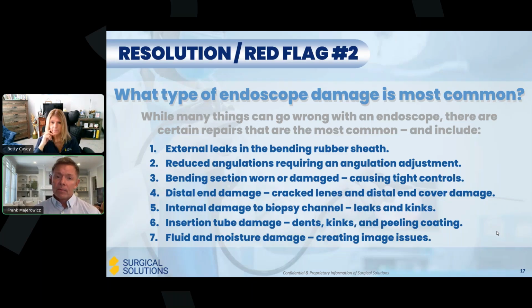Then there's internal damage. We see a lot inside the biopsy channel. Sometimes they come in with kinks where the insertion tube might have been over-manipulated or over-torqued or coiled up too tightly, leading to a kink or something inside the channel. And then also leaks. Leaks inside of the scope coming from the biopsy channel are very common as well. In most cases, a sharp instrument was being utilized, the forceps weren't closed all the way, or they were not in the best condition, causing gouges or cuts or scrapes inside the channels.